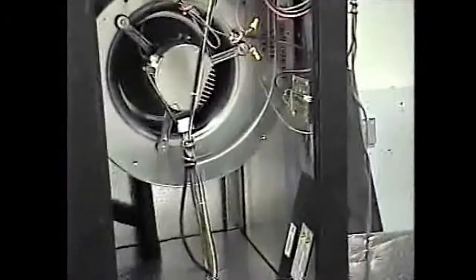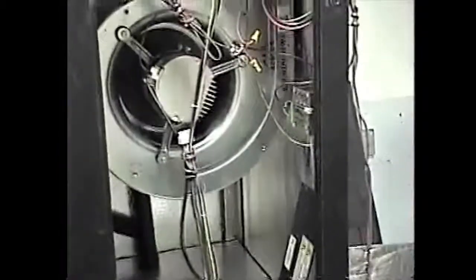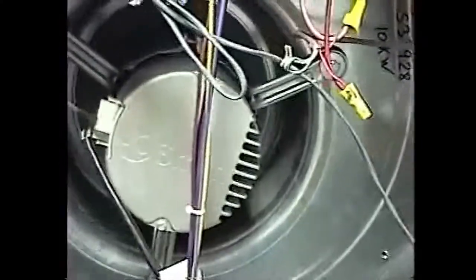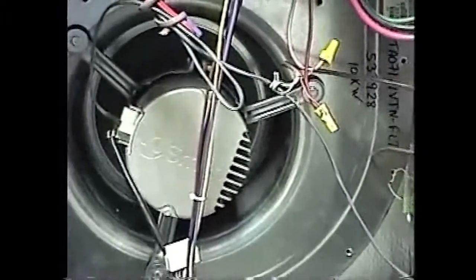The heating is what's tricky. The air will stratify in your duct, so be aware of that when you're placing the sensor. The motor you can see right now is running on its low speed, and I'm standing a foot away from the motor, and it's pretty difficult to hear it. It's not chattering, doesn't make any noise. My description is it runs as smooth as silk. Only what I'd expect from an air handler.